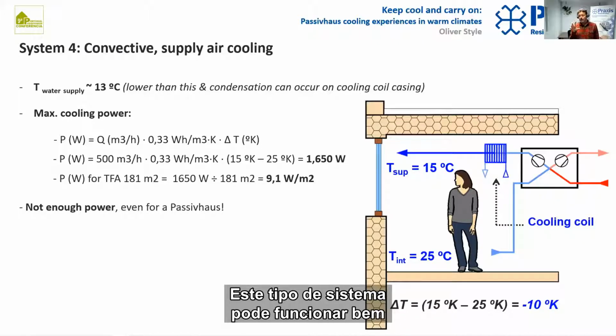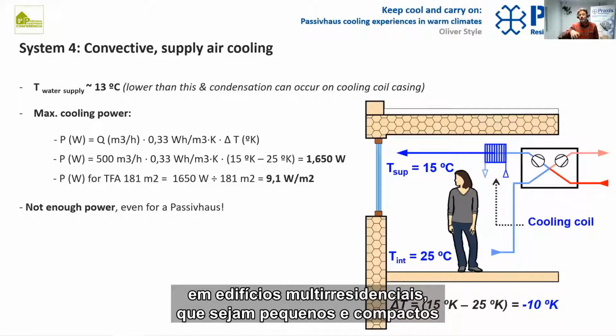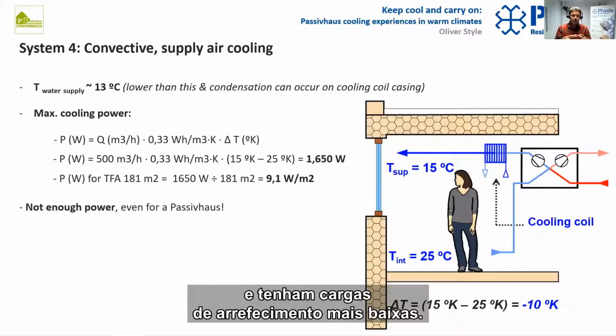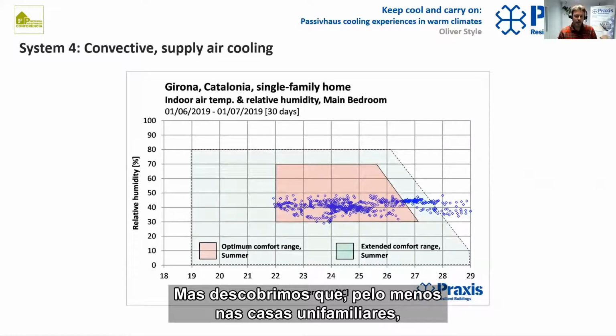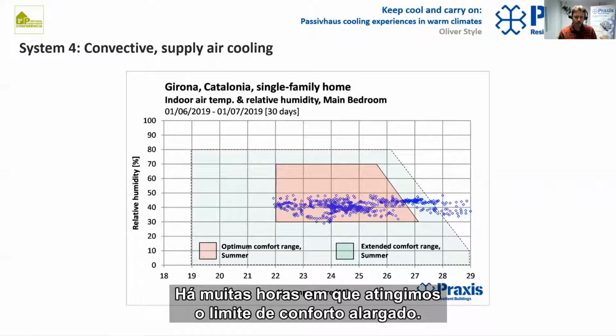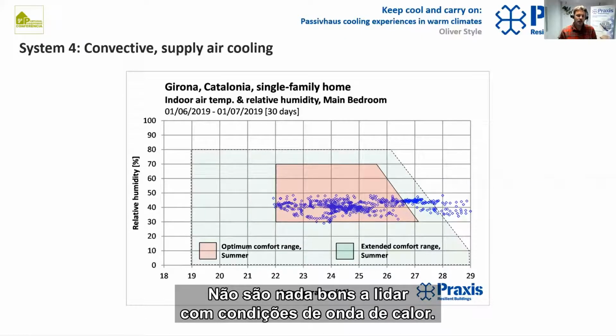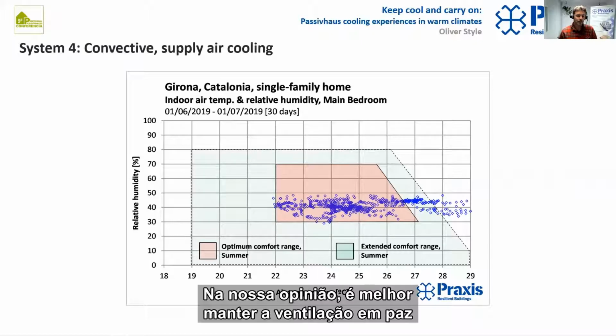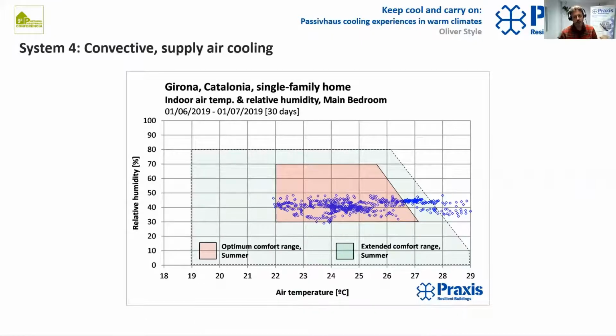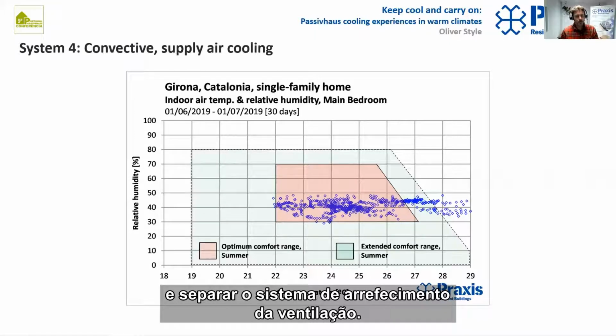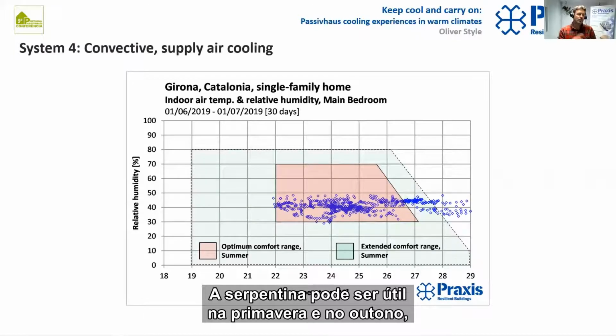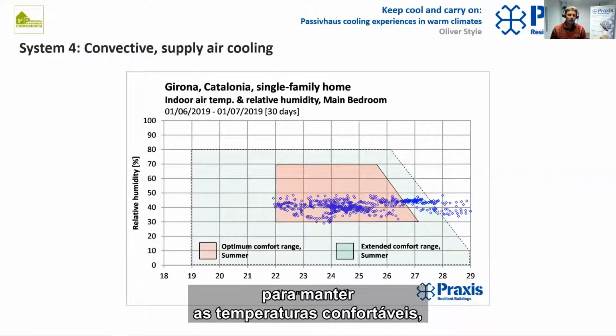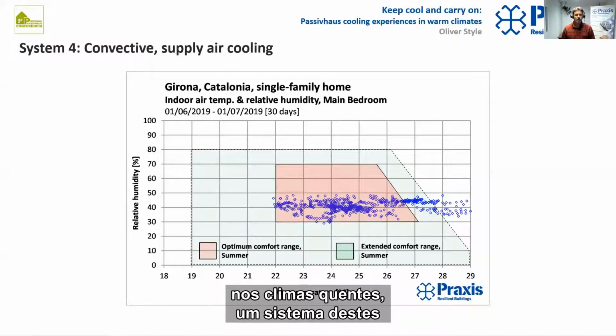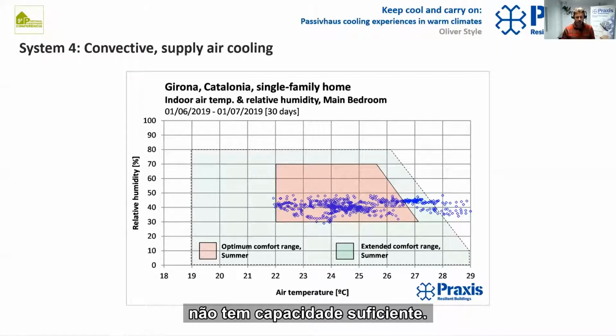This kind of system might well work well in multi-residential buildings, which are small, compact, and where cooling loads are lower. But what we found is that at least in single-family homes, we get results like this. So a lot of hours in which we move into the extended comfort range. Really not good at all at dealing with heat wave conditions. And in our opinion, it's best just to keep ventilation for ventilation and separate the cooling system from the ventilation. A cooling coil can be useful in the spring and autumn months just to keep temperatures comfortable, but really once you get into June, July, August in warm climates, it's just not enough power from a system like this.